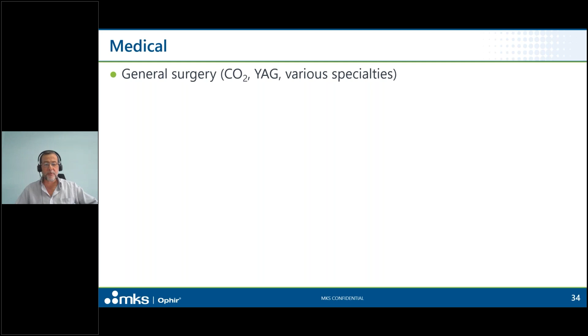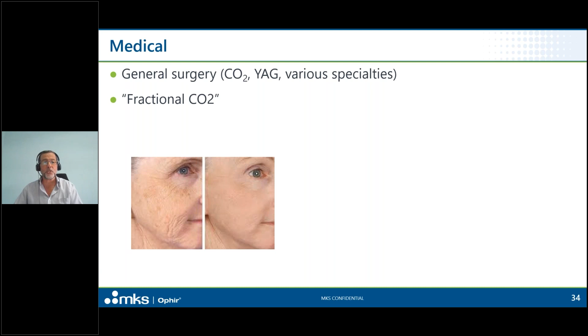Skin treatments are often based on laser beam systems that heat the area of skin where there's a problem, say sagging skin or wrinkles, and thereby stimulate growth of new tissue, which is going to be tighter and therefore more aesthetic. Some skin treatments, particularly skin tightening and skin resurfacing, if you're familiar with those, often use something called fractional CO2. It's a CO2-based laser, but with an added twist: it uses an array of pulsed pixel dots rather than treating the entire area at once, so that the exposure is a sort of reticle of dots pulsing rapidly, and then the whole array scans over the treatment area. This method leaves microscopic columns, as you can see in the diagram, of treated and untreated tissue throughout the treatment area. The idea behind this development was to shorten recovery time and reduce the risk of side effects.